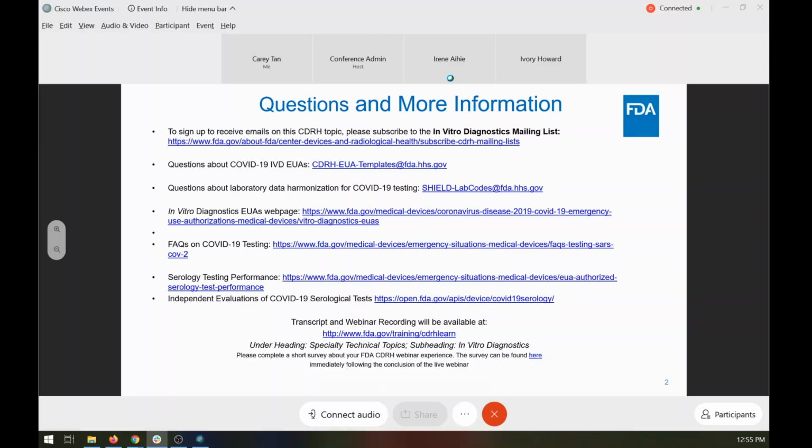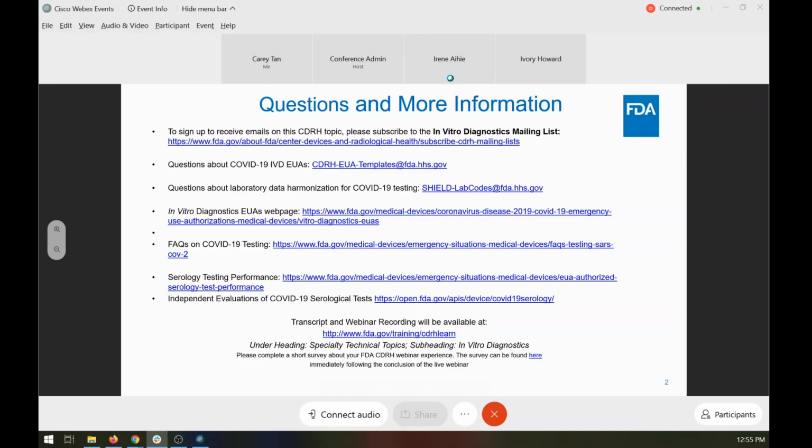So I think there are some recommendations in the new template for tests which have a lower sensitivity, and perhaps a serial testing strategy could be considered. And that's something that I don't think we have comments we could offer to you right now, but that's a strategy that you could propose, as long as you're hitting that 70% PPA mark with respect to a high sensitivity RT-PCR test. Okay, great, thank you. I do see that strategy for serial testing. Okay, that answers my question. Thank you.